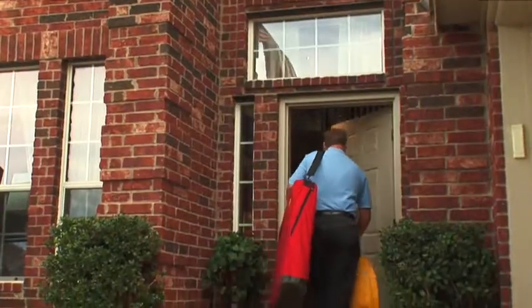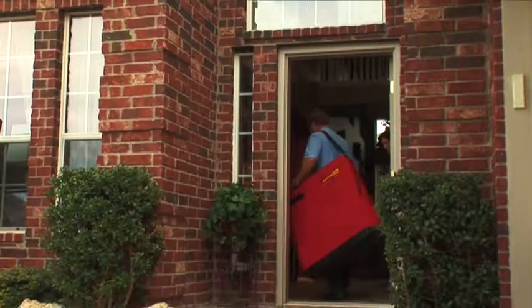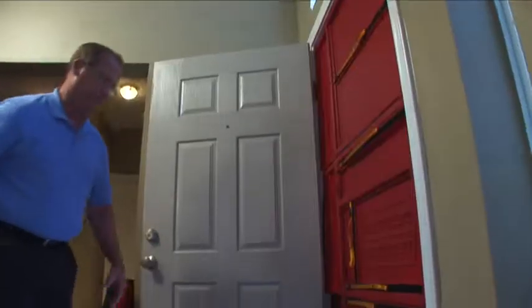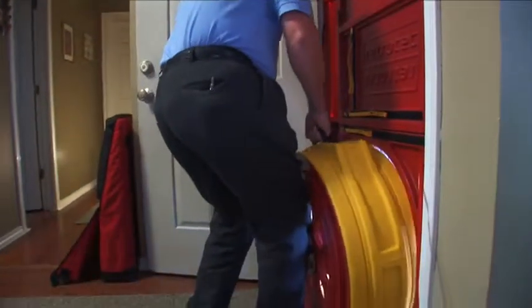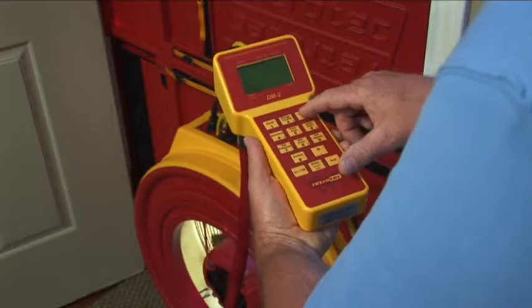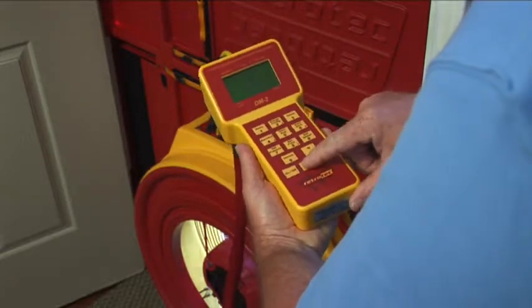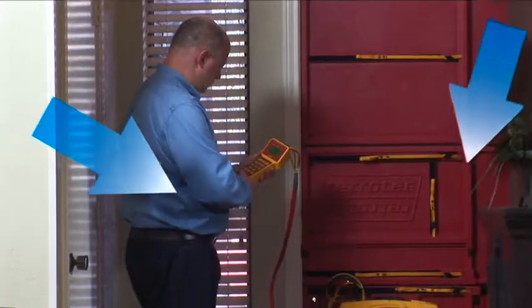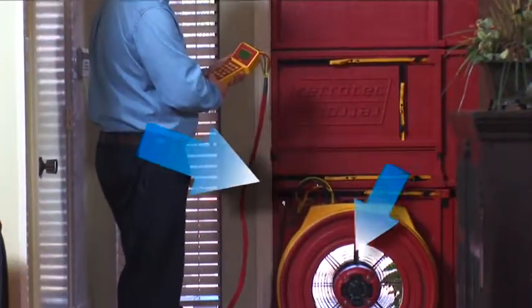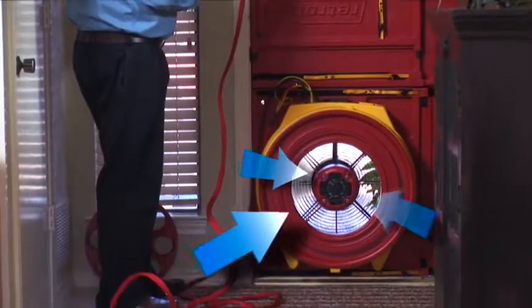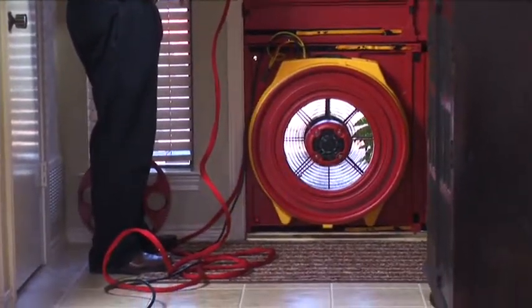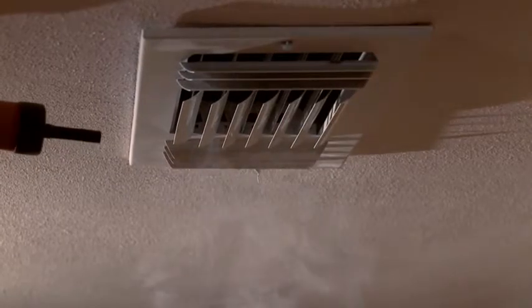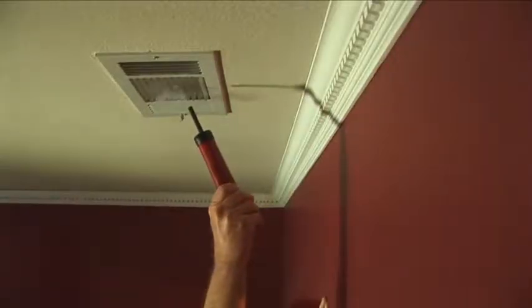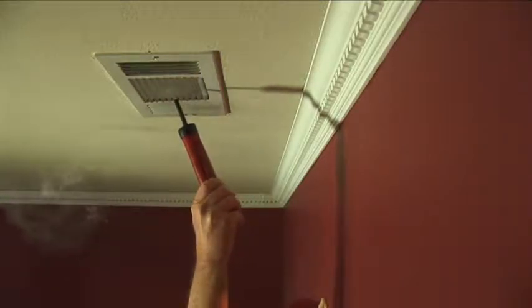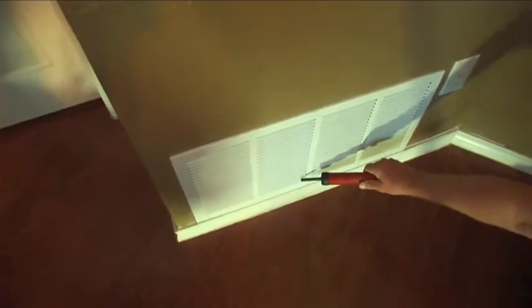To find out if your duct system leaks, have your HVAC contractor perform a duct leakage test using special instruments. These tests are done with the AC system circulating fan off. One easy check is to use a smoke puffer to see if any air is leaking out of the grills and registers while an infiltrometer blower door is running. Every bit of air the blower door is pushing out of your house has to be replaced by air coming in through the leaks. If the ducts don't have leaks, the smoke just sits there. But in most systems, outside or attic air will come in through both the supply and the return side, proving that there are leaks in the ducts.